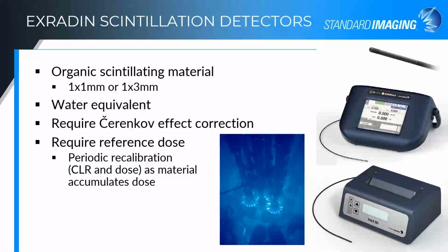So Cherenkov light is light that's produced by electrons moving faster than the speed of light in that particular medium. The standard description is that it's the shock wave in the light world, similar to the sonic boom that's generated when a jet travels faster than the speed of sound. It creates this blue glow that you see in the classic picture of the reactor coolant pool, but it's produced within that optical transfer fiber. And so depending how much fiber is in the beam, you would have more or less of this contaminating Cherenkov light.